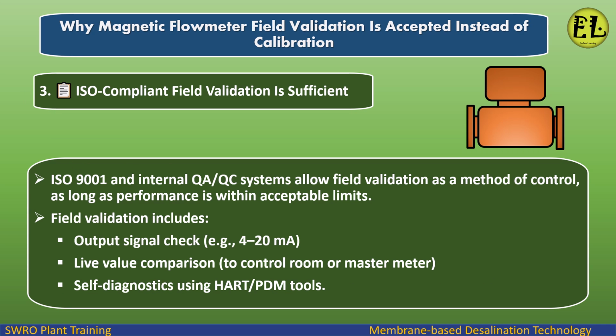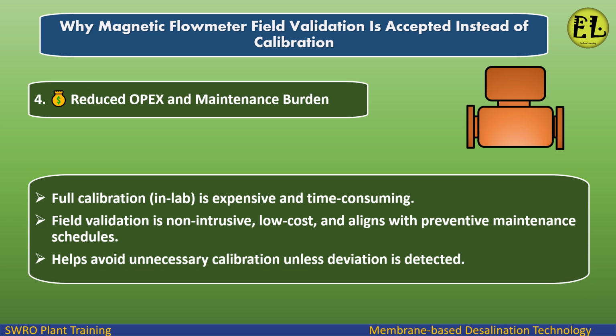ISO-compliant field validation is sufficient. ISO 9001 and internal QA/QC systems allow field validation as a method of control, as long as performance is within acceptable limits. Field validation includes output signal check, for example 4 to 20 mA, live value comparison to the control room or master meter, and self-diagnostics using HART/PDM tools. Reduced OPEX and maintenance burden.